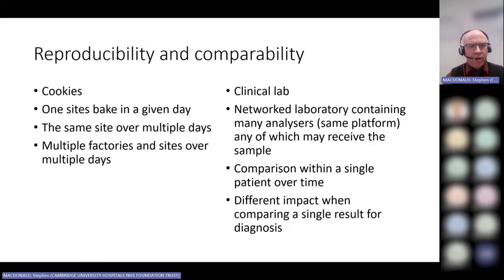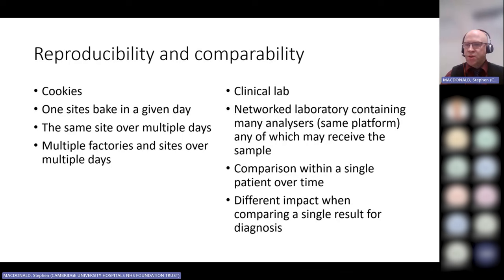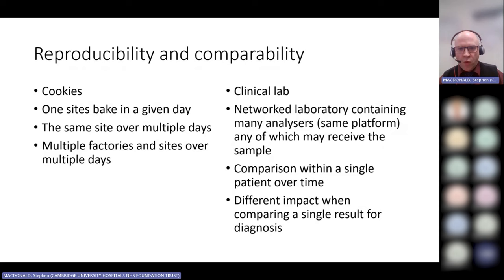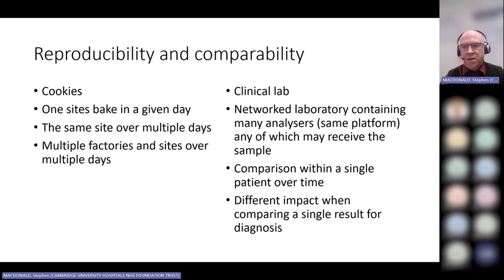By measuring our variation, it allows us to quantify reproducibility and comparability of results. Going back to the cookie analogy: how consistent can we make our bakes in a given day versus across different days, different factories, or different sites? Our CVs allow us to do that on an individual analyzer basis, but also across network laboratories and large hospital networks spanning large geographical areas, comparing and contrasting performance across those ranges of activity.